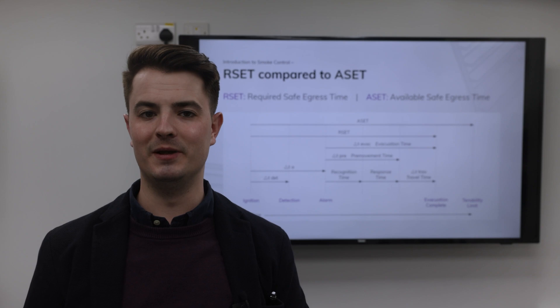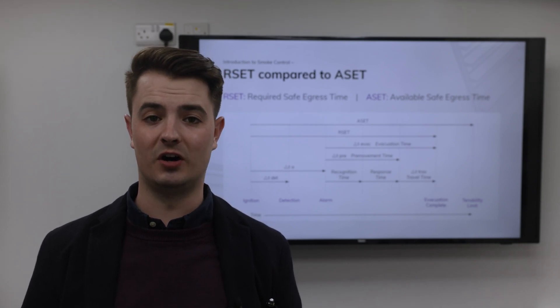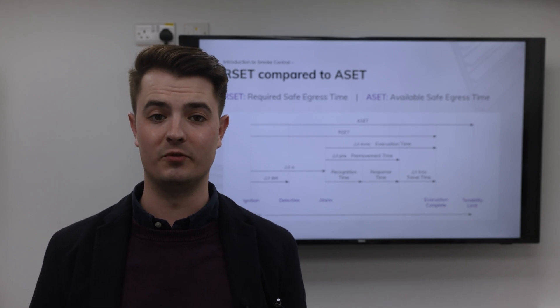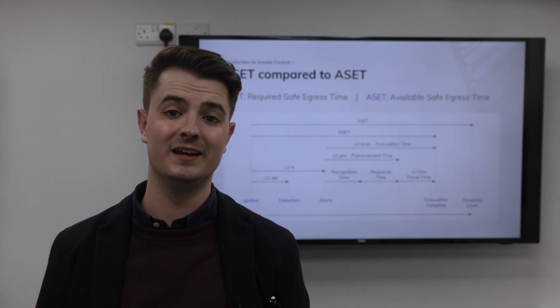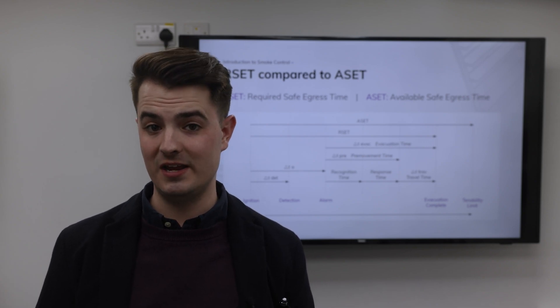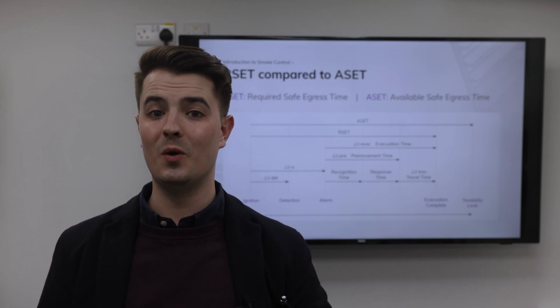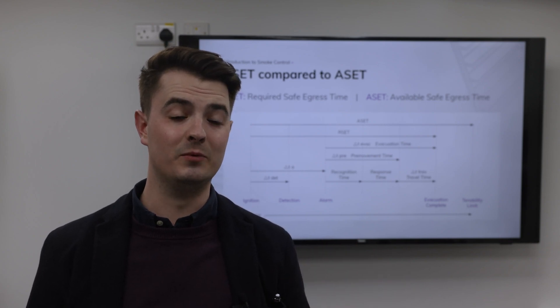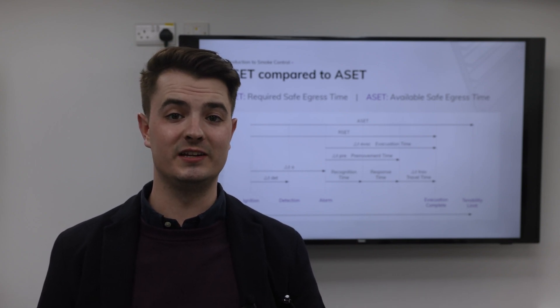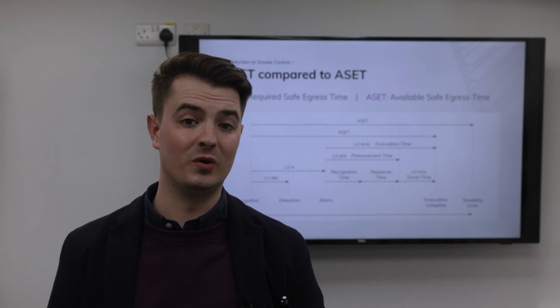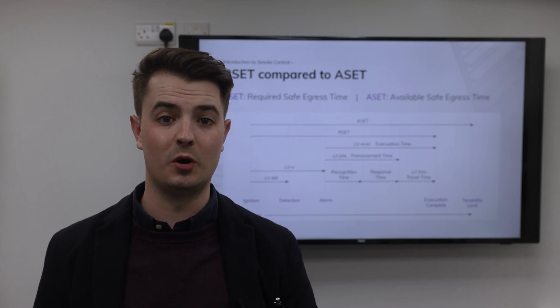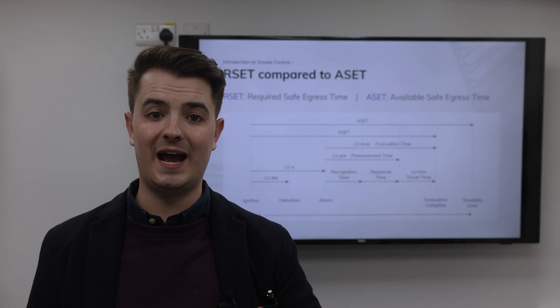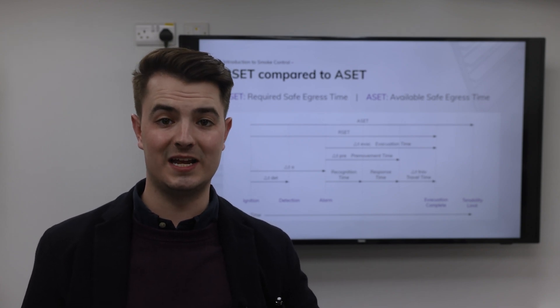The ASET is the length of time we can maintain tenability in the fire escape routes. We've covered tenability in a previous video, but what we're talking about is conditions that don't cause incapacitation — that's what we mean by tenability. So ASET is how long we can keep the escape routes safe for people to escape through. When designing a building, we can build up the ASET using various things such as the type of non-combustible material or fire load, ceiling heights, smoke ventilation systems, sprinklers, and so on. In a very loose sense, the more passive and active fire protection methods we add, the longer the ASET becomes.